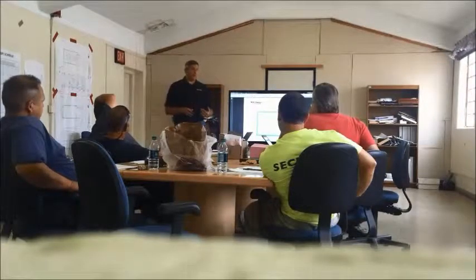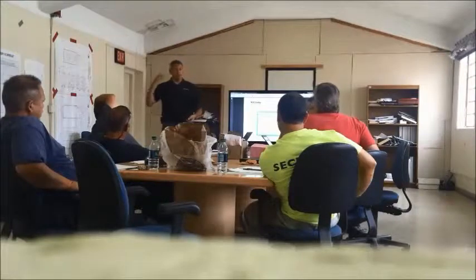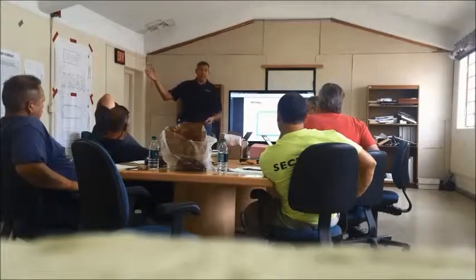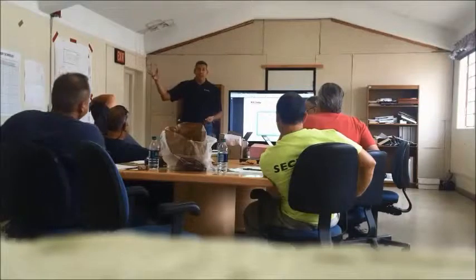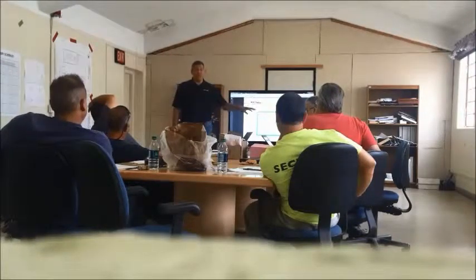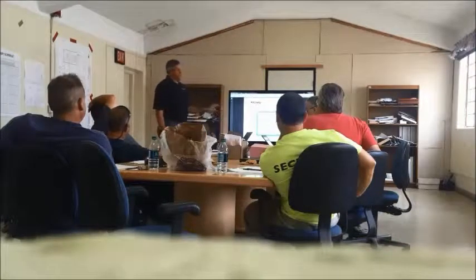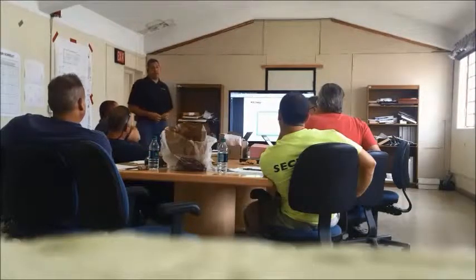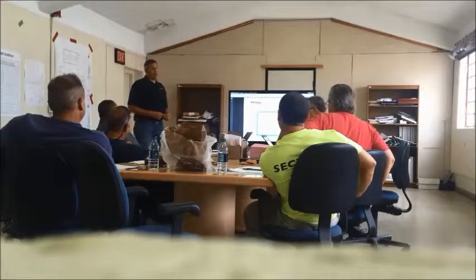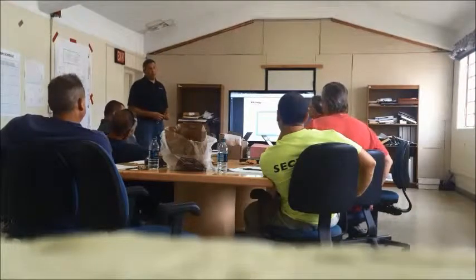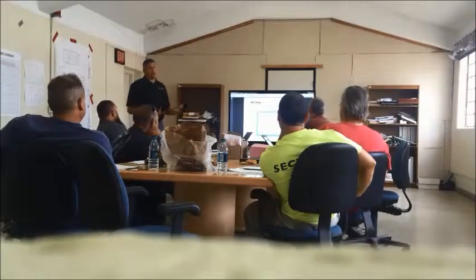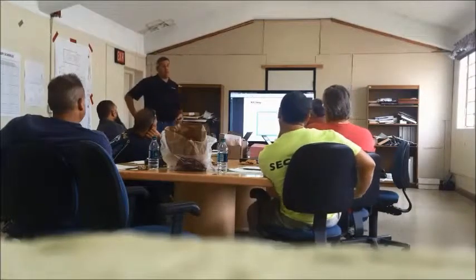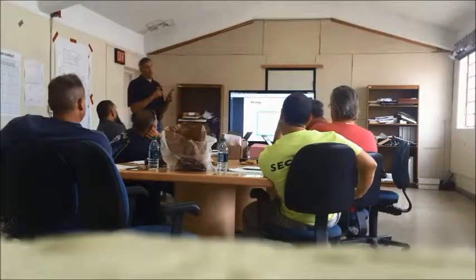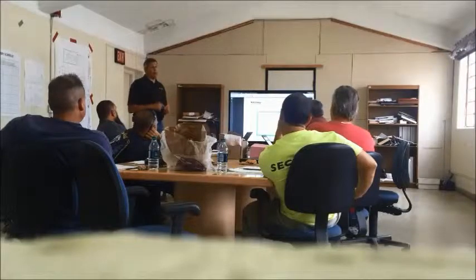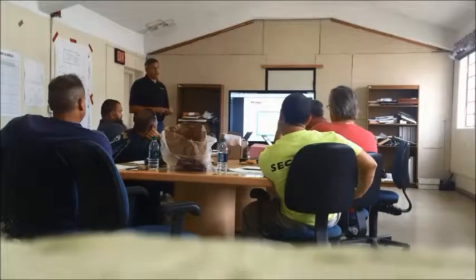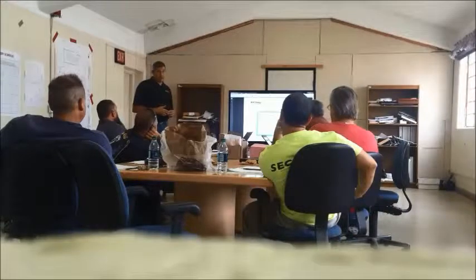So we had to go through elaborate means of controls to try to find a solution, which was basically try to tell one fan to be the lead and go to a certain speed, and at that point if it goes into bypass, you have other issues. So what's nice here is that this logic internally, they've incorporated a fire alarm mode. So we wire to that through a fire alarm module. If that module is activated, then it'll disregard standard control mode. It's going to flash fire alarm mode, and it allows us to give a certain set point in that condition, which at this point is the lowest value we can set for is 0.6.